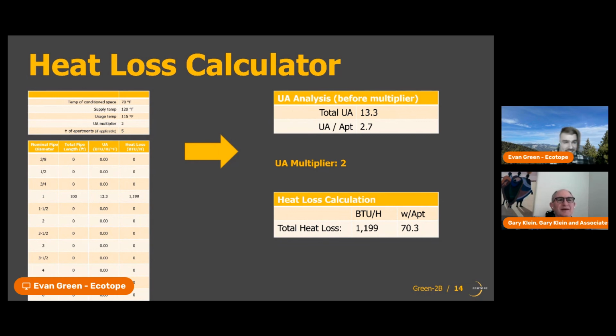Okay, great. So what we'll get as an output from this calculator is going to be the total heat loss in the entire loop and the watts per apartment heat loss, which I like to reference because our EcoSizer tool that sizes heat pump water heating systems has a watts per apartment input for the recirc losses that we're assuming. The standard assumption in that sizer is 100 watts per apartment with a 1.5 safety factor. So it's a pretty conservative heat loss, so then we make sure we don't undersize that temperature maintenance heater.